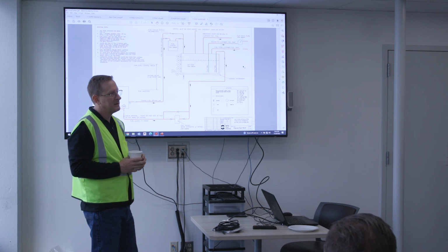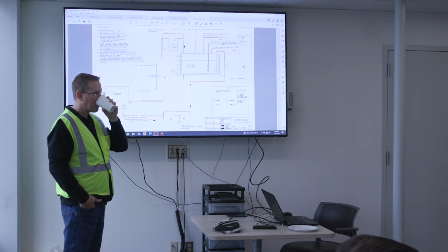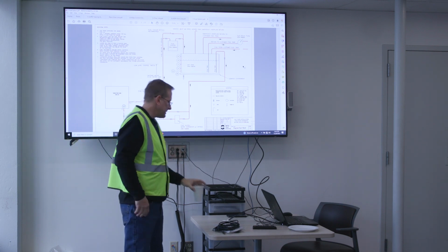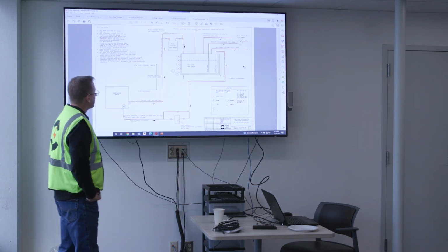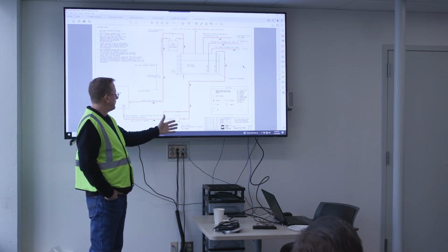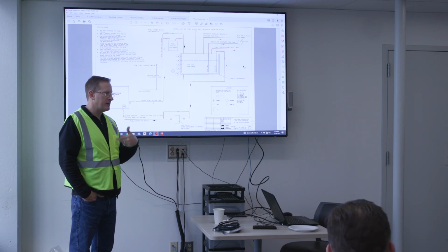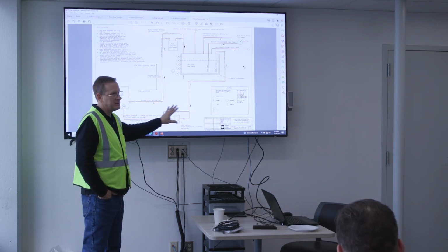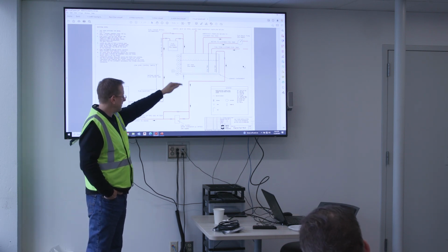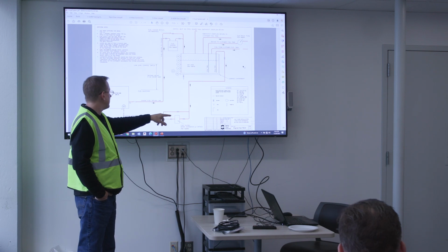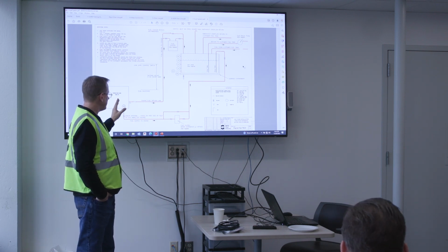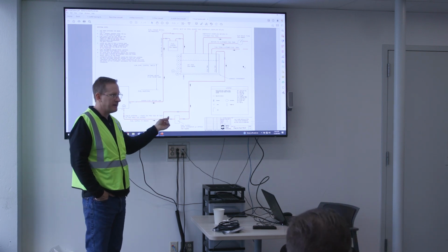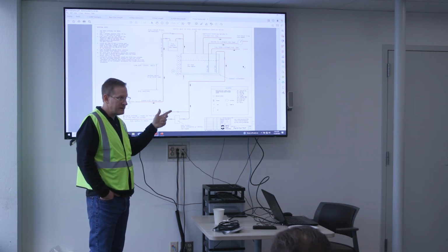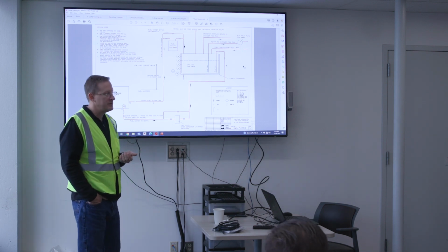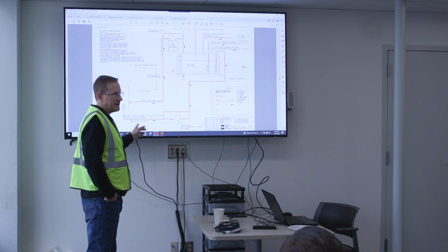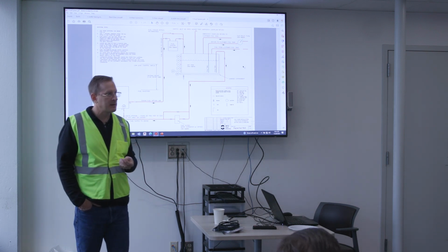So when we have to change those filters or whatever, then we have to reprime it? Typically, yeah, when you change the filters, you don't necessarily have to reprime it, but you want to go ahead and run the engine and then let it run a little bit so that it gets all that air out of the system that it might be in it. The gravity feed that will come into it once you're done changing out the filter is going to be enough to maintain your ability to start the engine, but there might be a little bit of air in there that you'll want to run the engine for a few minutes in diesel test mode, for example, or in idle mode, just to make sure that you run some fuel through it so that it gets all the air out of the system. So you won't lose prime?